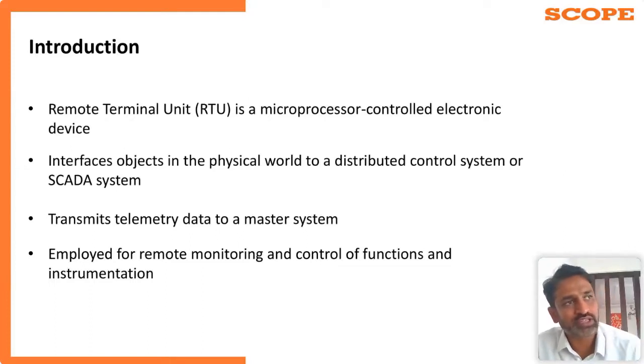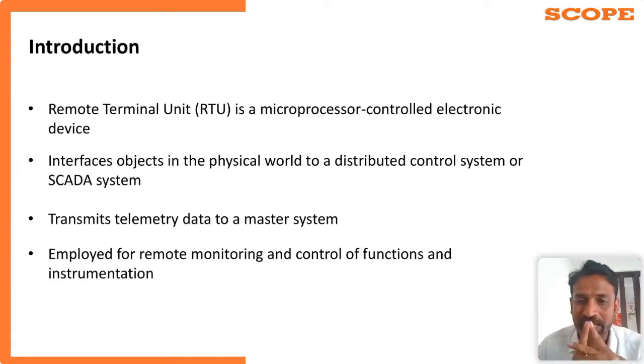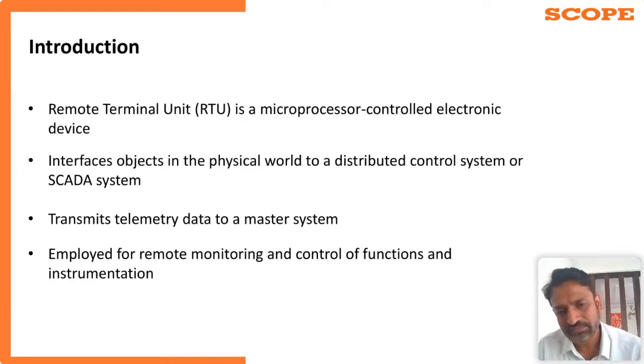Suppose today what we are doing in the substations' control room is, if you go to the old substations and old control rooms, there are two very big different panels. One is the control panel and the other is the relay panel. The control panel is completely mechanically driven. That will resemble your primary equipments. What is the breaker status? There is a semaphore indicator used for showing the breaker status or isolator status, even the meters data or alarms, annunciations. But the problem is that if you are using those sort of old systems, you may require more space, and also human interface is more important in that one. But you want to make it so that all this data should be brought to one PC. Then what you need to do, you can use one sort of device which will collect the data from the field and give it to you on the system. So that is the importance of this particular RTU.